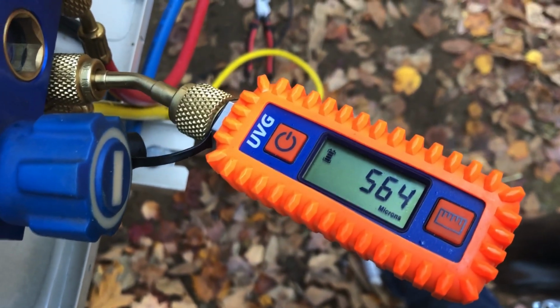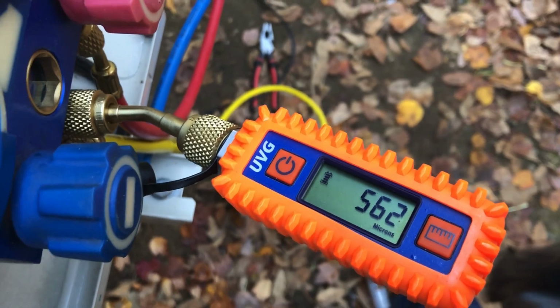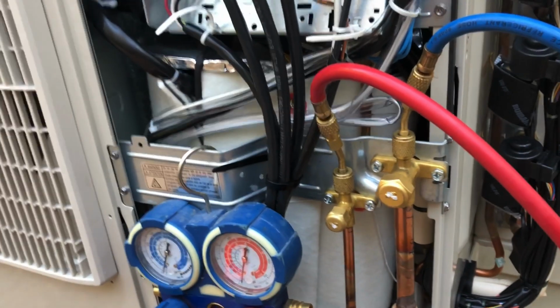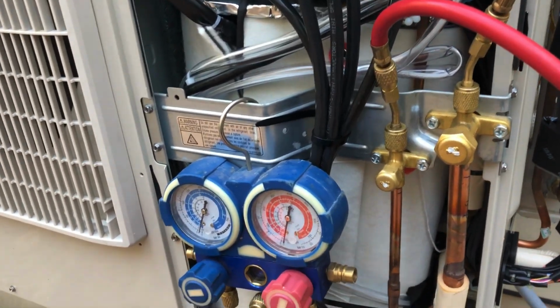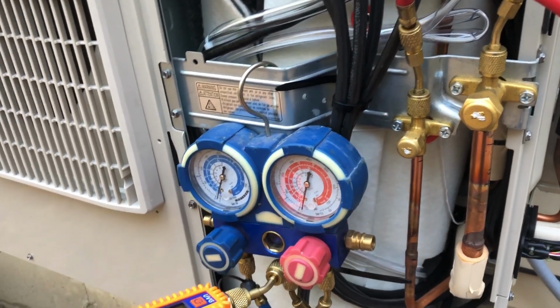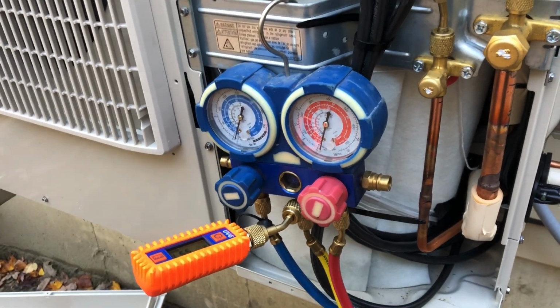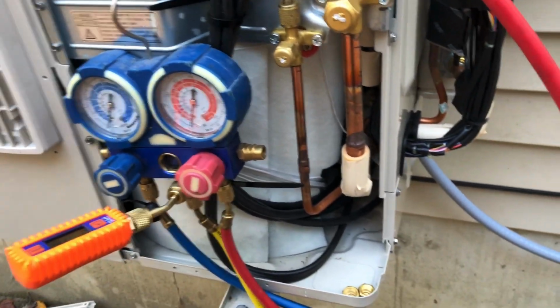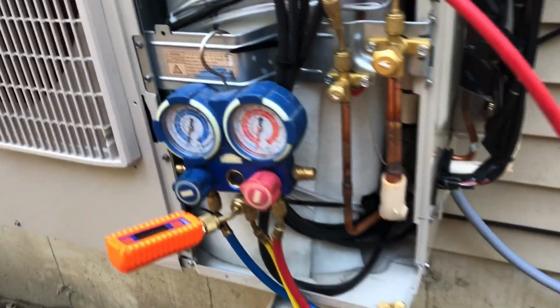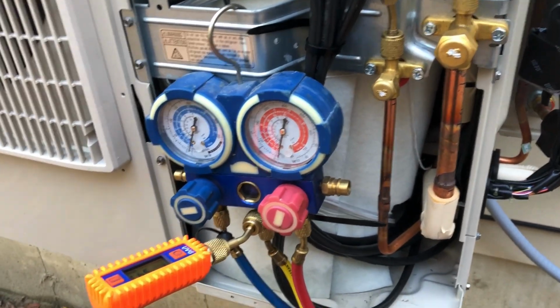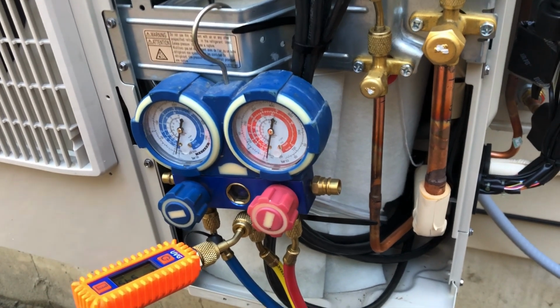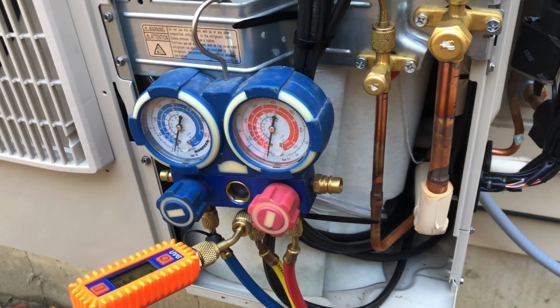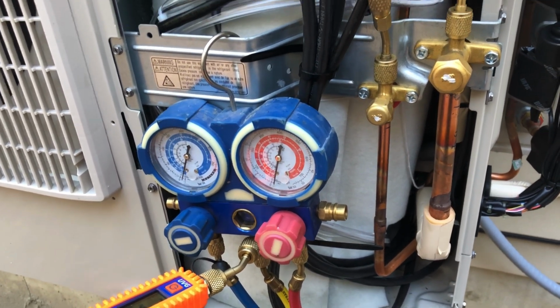It's still dropping really quick. If you're not able to drop below 1000, if it's consistently not dropping, then that means you have a leak. It means you're sucking air somewhere. If it drops below 1000, you're pretty good. I'd like to see it drop below 500 and stay there. I'm going to leave this vacuum running for a couple of hours, and then I'll come back. Since it's going to be dark when I get back, I'm going to end the video here because this is going to run for a while.